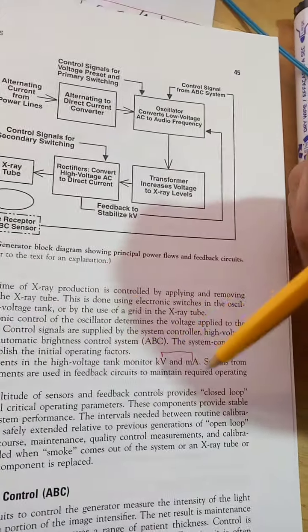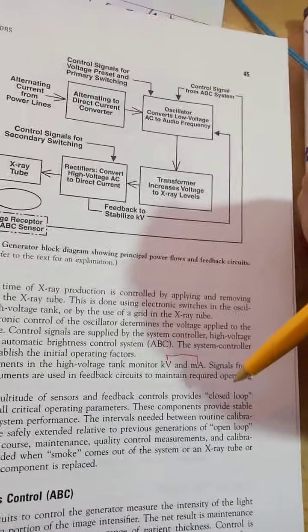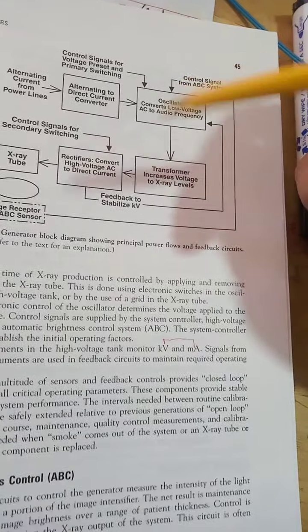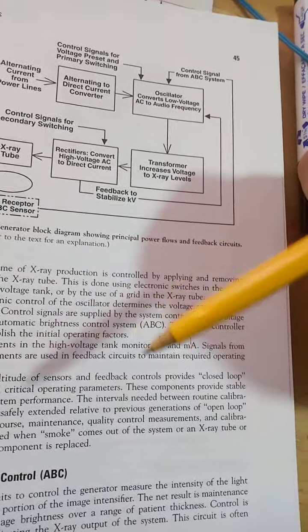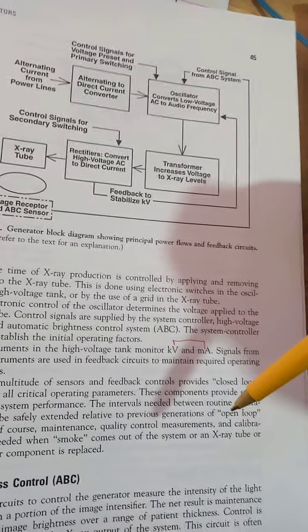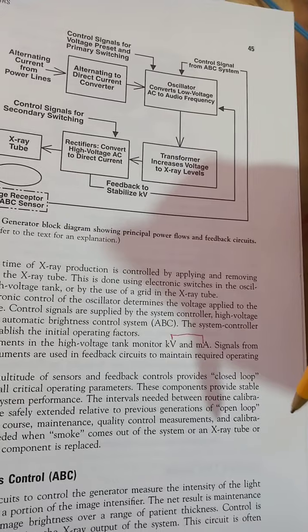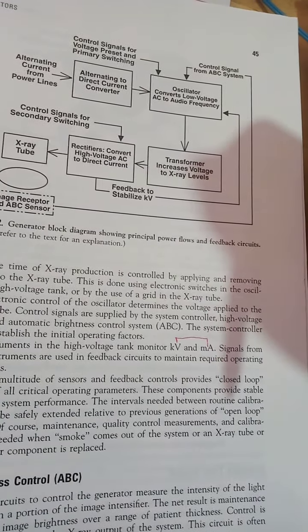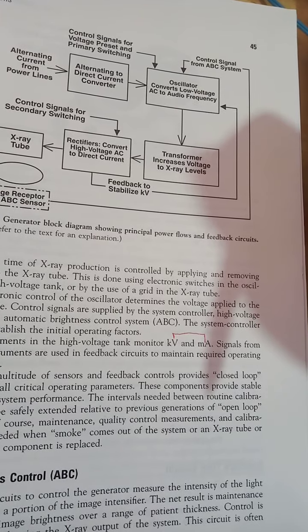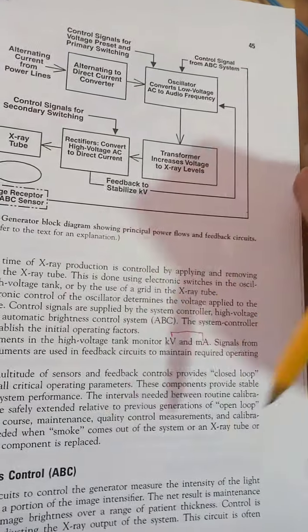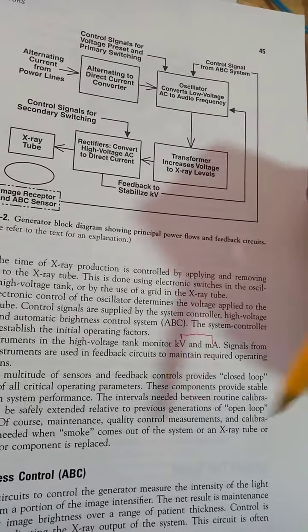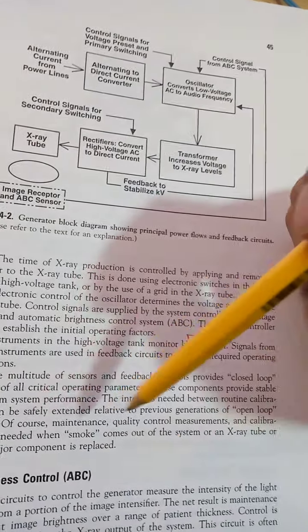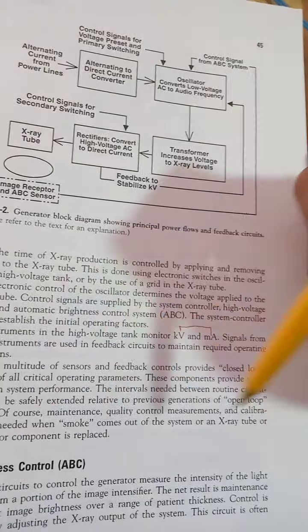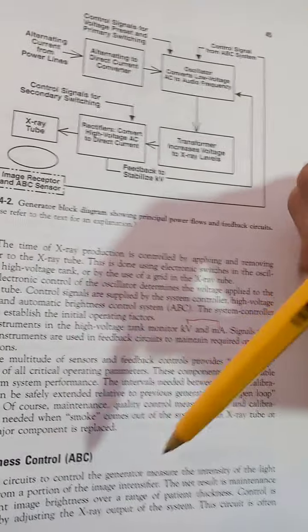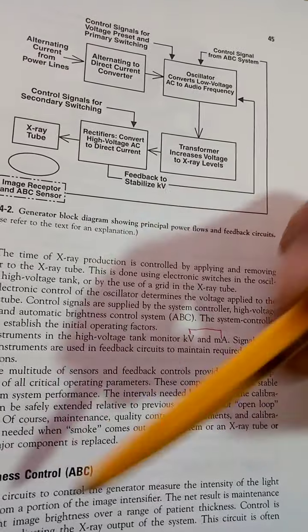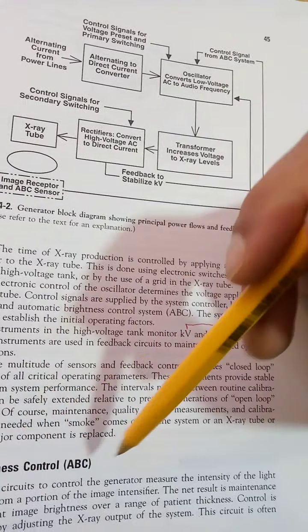Signals from these instruments are used in feedback circuits to maintain required operating conditions, so it's slightly homeostatic. The multitude of sensors and feedback control provides closed-loop control of all critical operating parameters. These components provide stable long-term system performance. The intervals needed between routine calibrations can be safely extended relative to previous generations of open-loop systems. Of course, maintenance, quality control, measurement, and calibration are needed when smoke comes out of the system, or an X-ray tube is replaced, or whenever a major component is replaced.